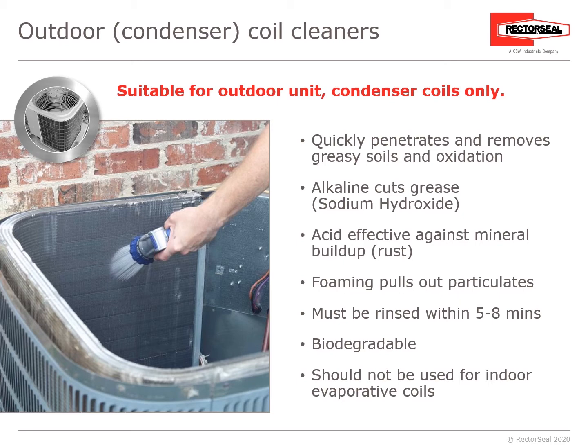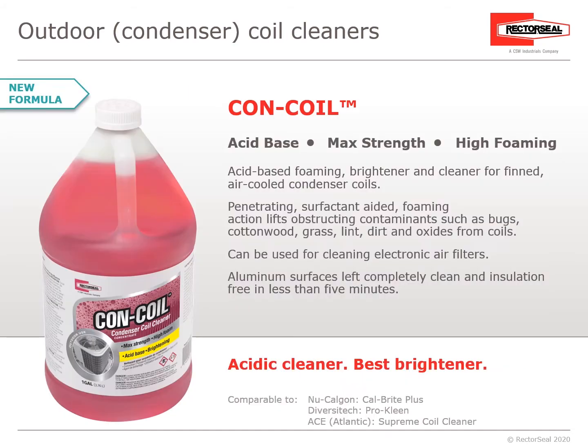The foaming pulls out the particulates. But all of these really need to be rinsed within 5 to 8 minutes after applying. You want a product that's biodegradable, safe for all the vegetation around the unit. Condenser coil cleaners, however, should not be used for indoor evaporator coils. The first condenser coil cleaner from RectorSeal, we have CON-COIL, a new formula.